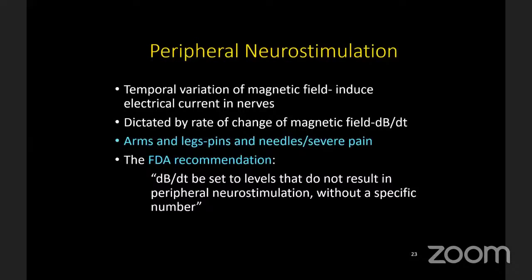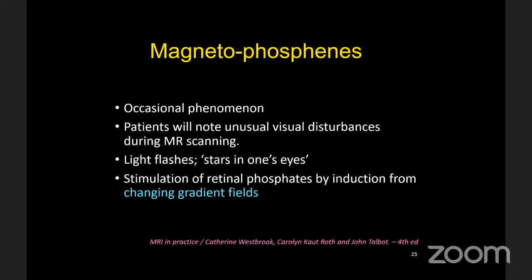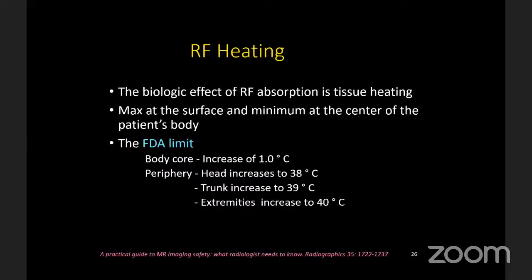In peripheral neural stimulation effects, patients can experience tingling or severe pain in the arms and legs. The FDA recommends that gradient strength be set to levels that do not result in peripheral neural stimulation. This is a greater risk for sequences involving high bandwidth rates and rapid gradient switching. Magnetophosphenes are a related phenomenon where the patient notes unusual visual disturbances during MR scanning — stars or light flashes in one eye — resulting from induction by changing gradient fields. Radiofrequency heating is a biological effect of radiofrequency absorption, maximum at the surface and minimum at the center of the body. The FDA has defined limits: body core increase of 1°C, with the head not exceeding 38°C, trunk 39°C, and extremities 40°C.